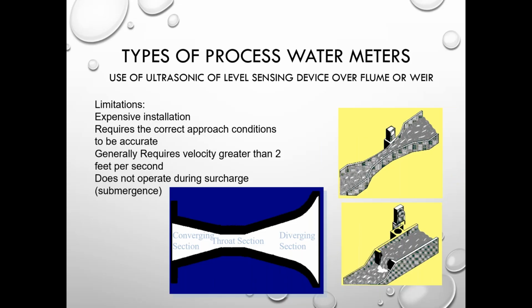On these flumes and weirs, you'll have a converging section, a throat section, and a divergent section. So as the flow comes through, it converges into the throat and leaves. I have seen some facilities where the flume is actually put in backwards, and that makes it very difficult to calibrate, and it doesn't work very well in that situation. So when you see flumes and weirs, you want to make sure they're put in the correct direction.